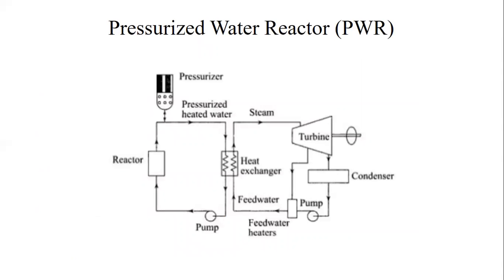The first type is the pressurized water reactor. The excellent properties of water as a moderator and coolant make it a natural choice for power reactors, and the pressurized water reactor has been extensively developed in the United States of America. The most important limitation on the pressurized water reactor, that is PWR, is the critical temperature of water, which is 374 degrees Celsius. This is the maximum possible temperature of the coolant in the reactor, and in practice it is considerably less, possibly about 300 degrees Celsius, to allow a margin of safety.